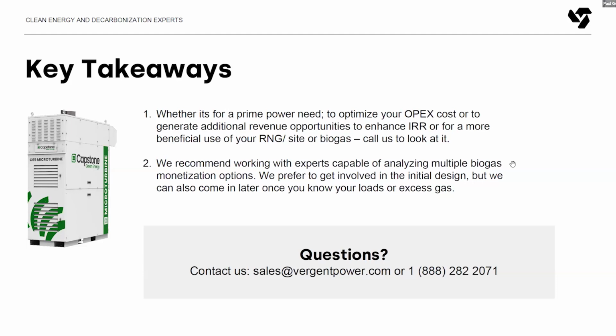So to the point about SCRs - do you supply SCRs, or do you not require them? We do not require them. We do have a passive catalyst option we can supply that deals specifically with CO, carbon monoxide, but that's for very rare projects, such as greenhouses where we're direct exhausting into the greenhouse and need the exhaust as clean as possible. But we don't do SCRs, and they're not needed in any jurisdiction we do business in - including California, and this project in New Hampshire is another example. They have pretty tight air emissions requirements there, and we were well within the limits.